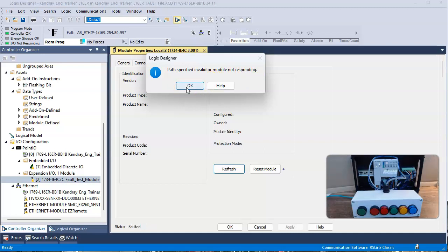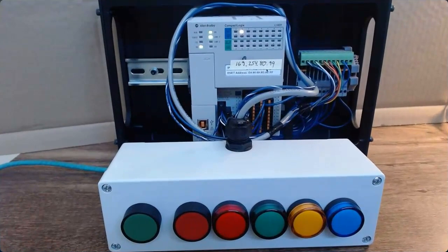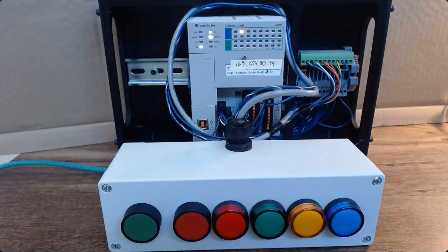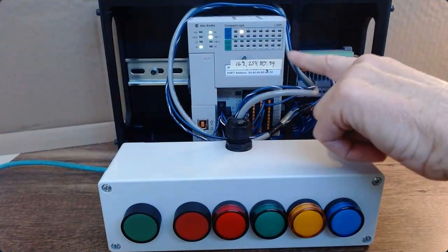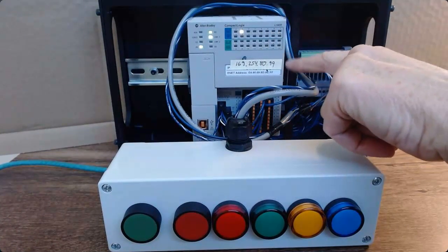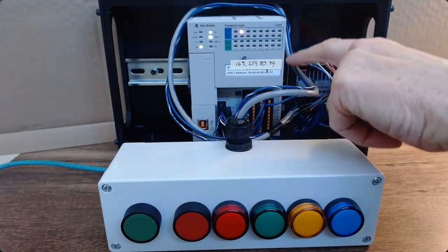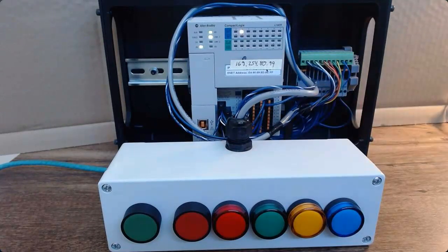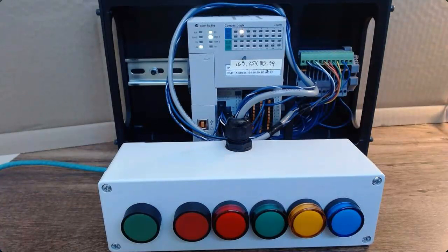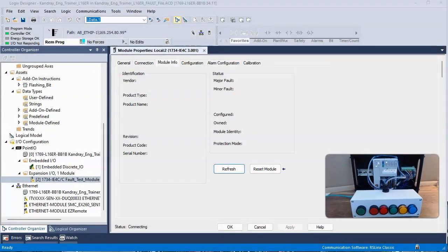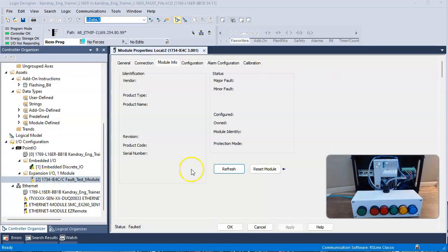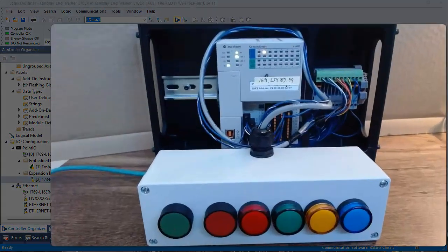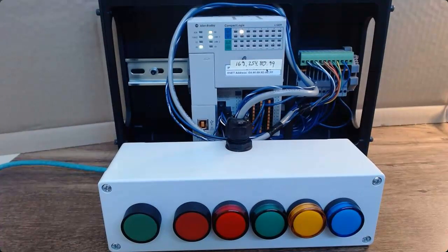And if you may have noticed that since this is a test, this particular PLC has no additional modules assigned to it. Consequently, the IO configuration thinks that we have an expansion module when in reality we don't, which generates the fault whenever you try to go to run.